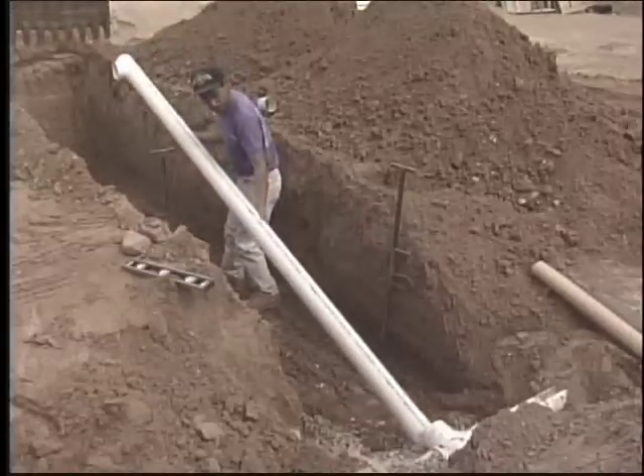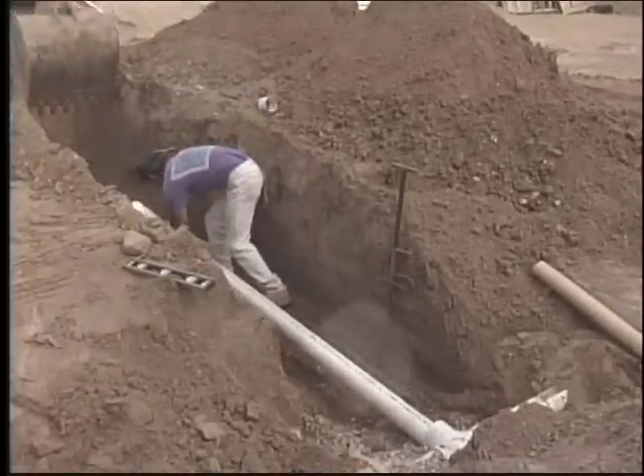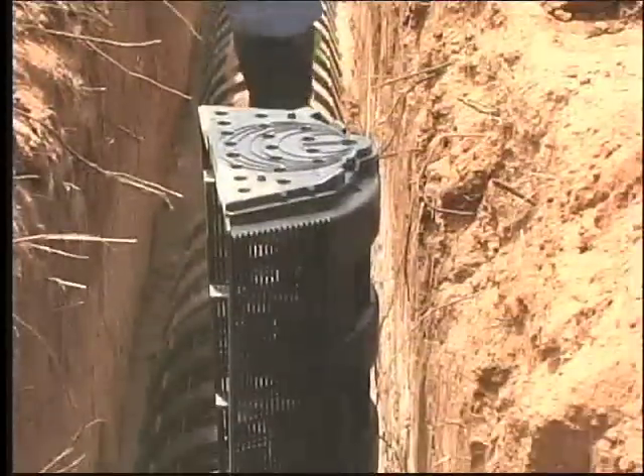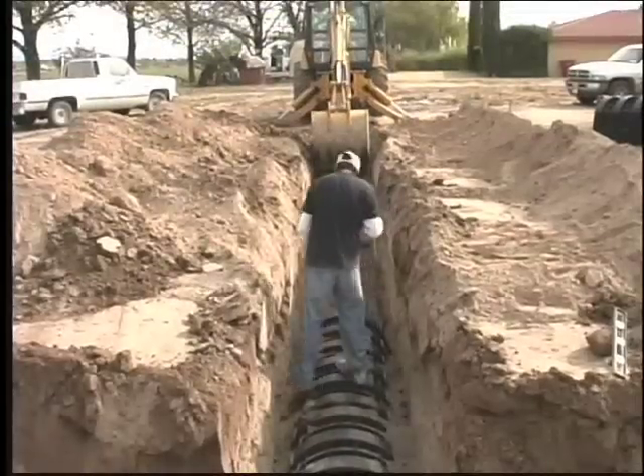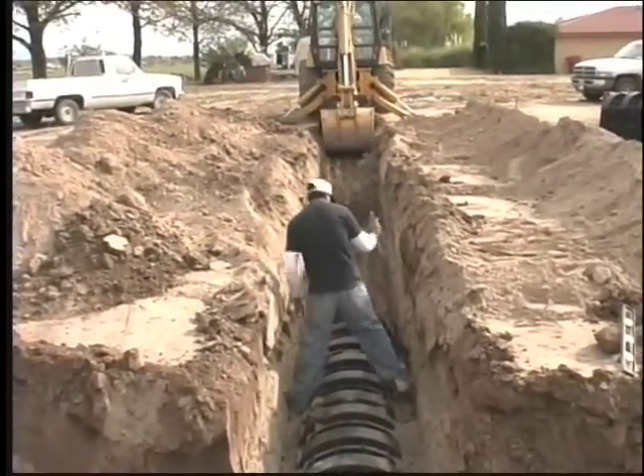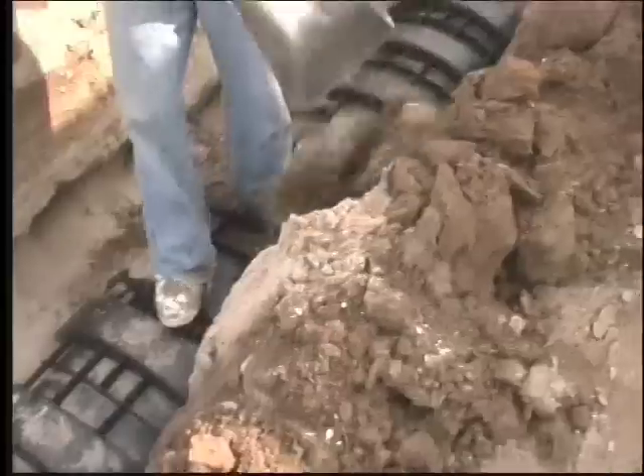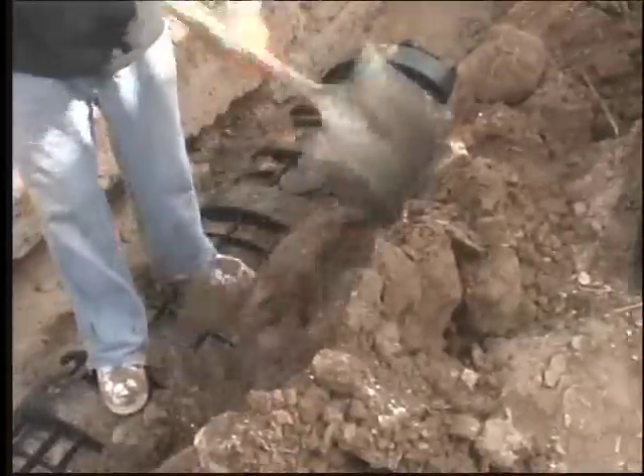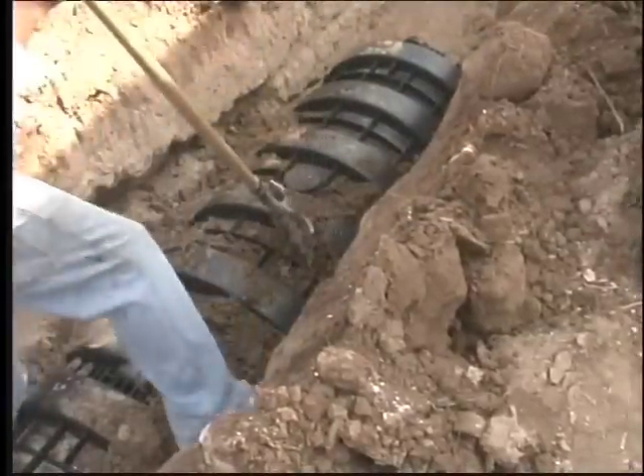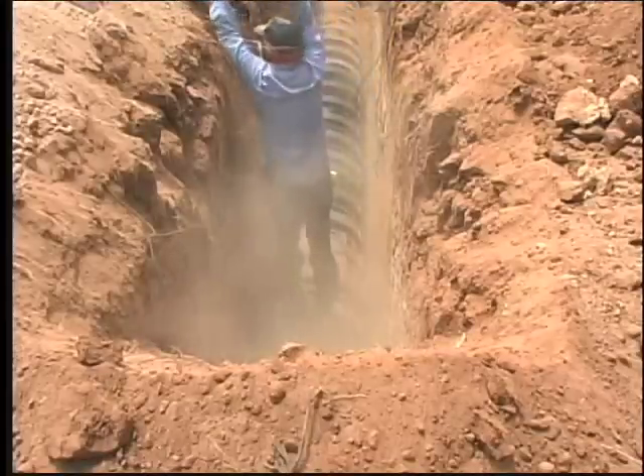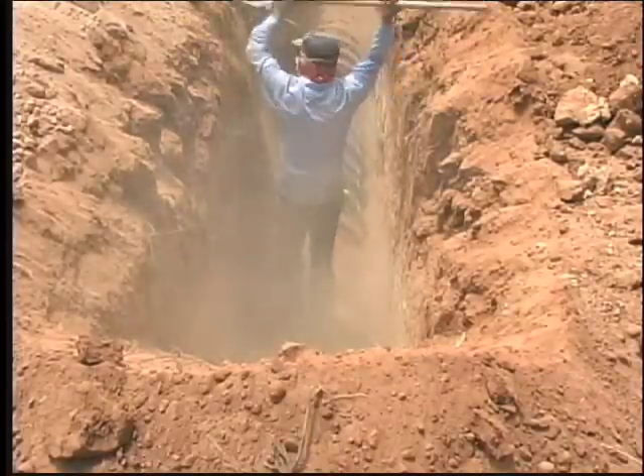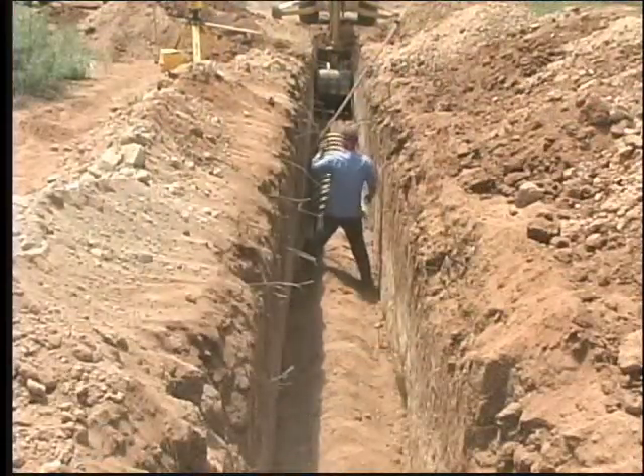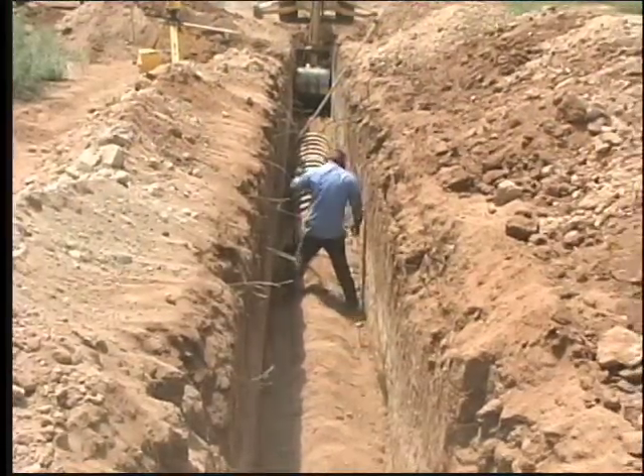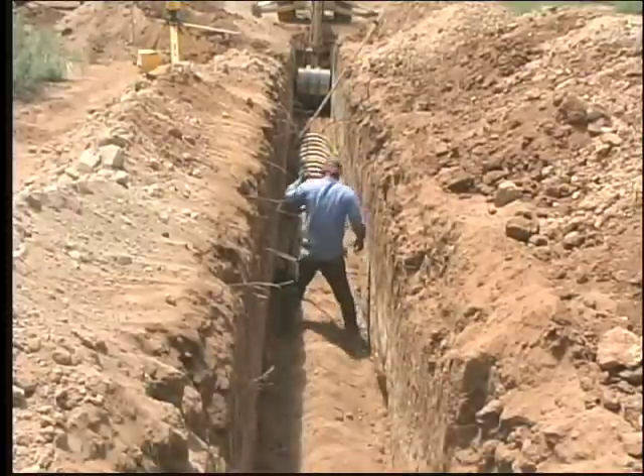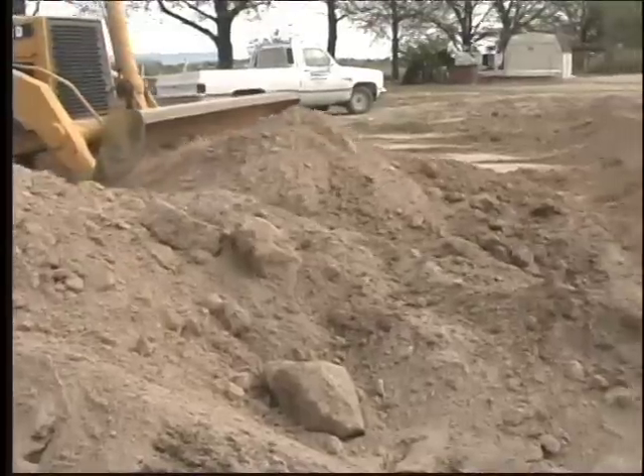If the system is to be either a loop system or a series system, use an open end plate instead of the closed end plate. It is critical with these chamber systems that the sides of the systems be filled prior to backfilling. This provides support for the arch so that the chamber does not collapse or cut into the underlying soil during backfilling. Fill the sidewall area to the top of the slots with native soil and walk the soil into place. Now the chamber system is ready for the trench to be backfilled.